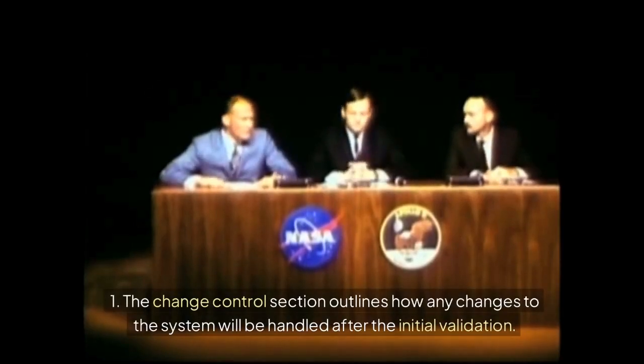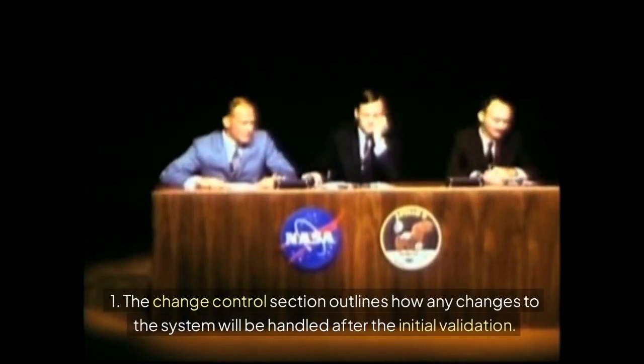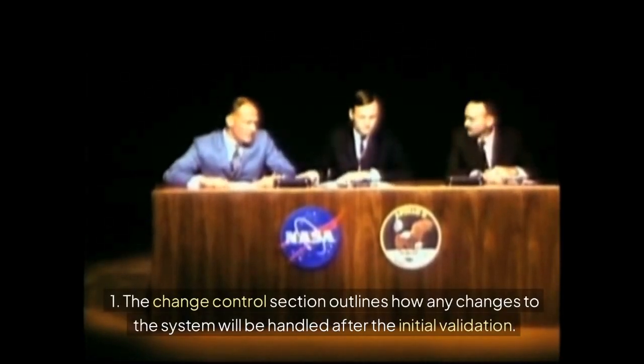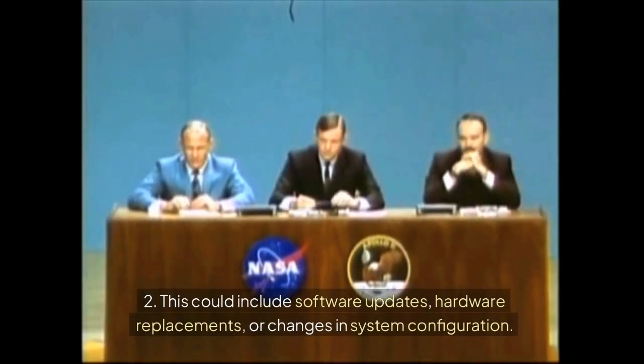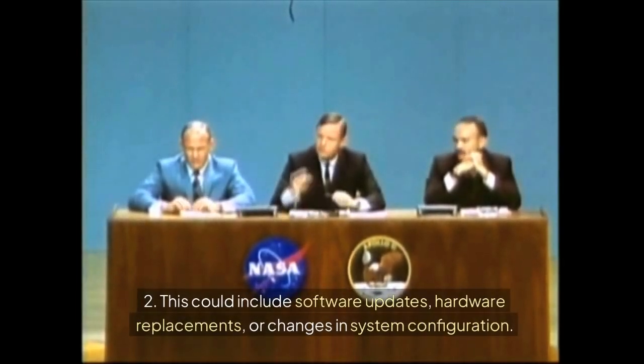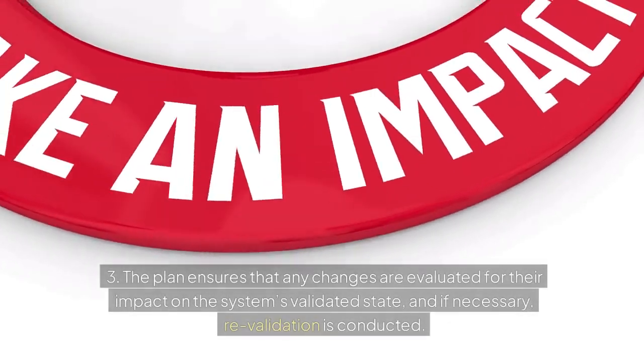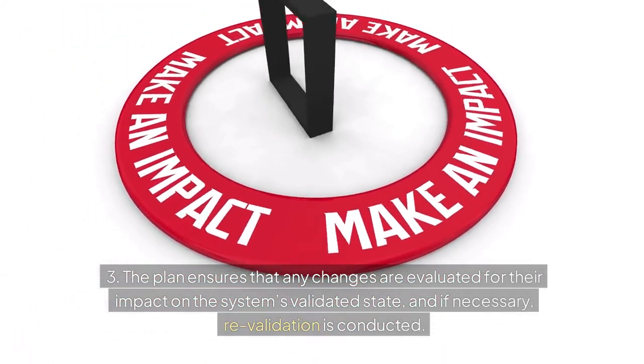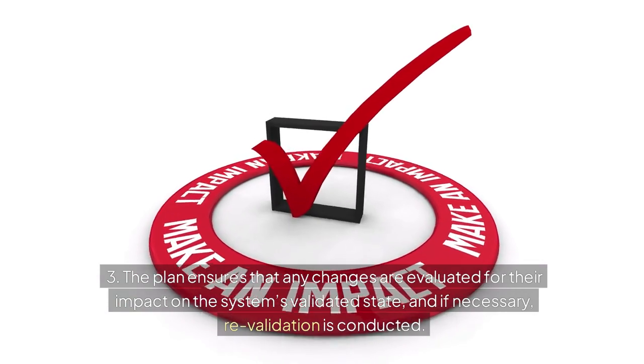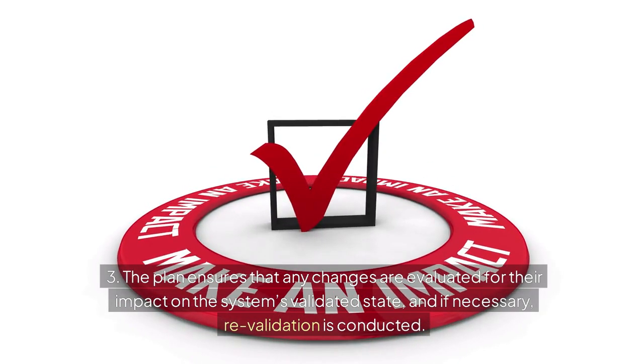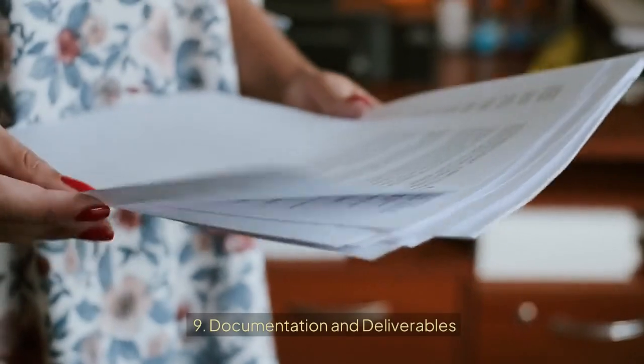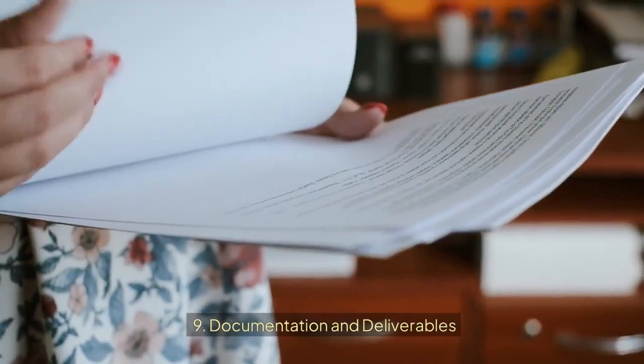8. Change control. 1. The change control section outlines how any changes to the system will be handled after the initial validation. 2. This could include software updates, hardware replacements, or changes in system configuration. 3. The plan ensures that any changes are evaluated for their impact on the system's validated state, and if necessary, revalidation is conducted.